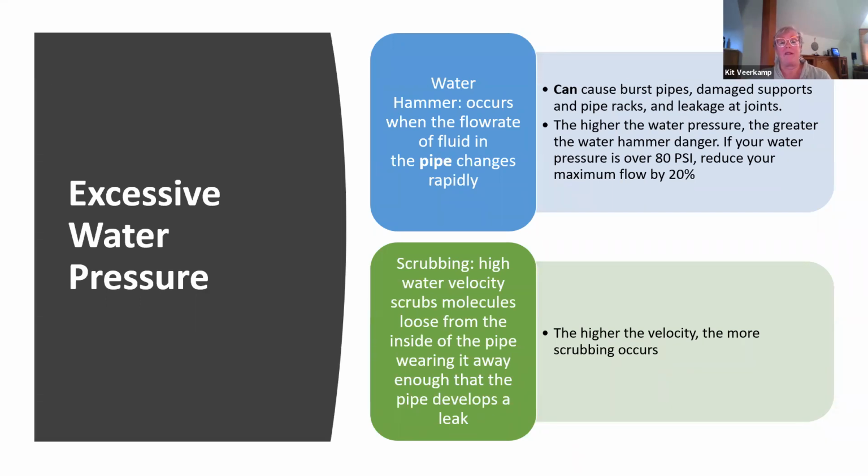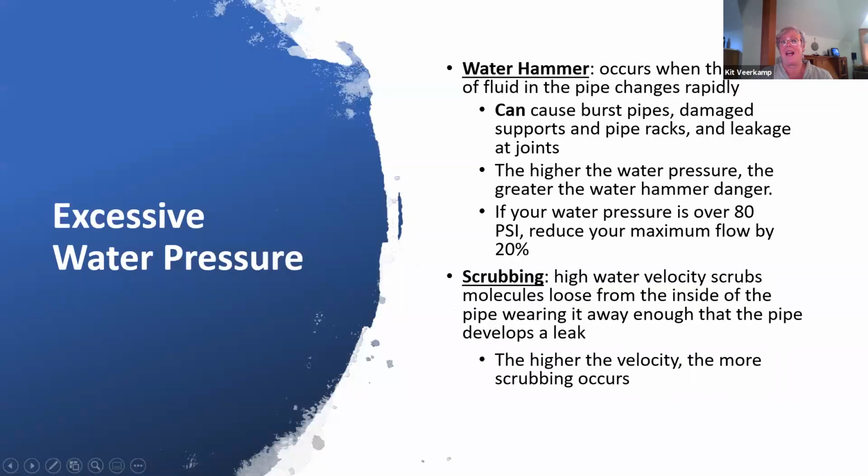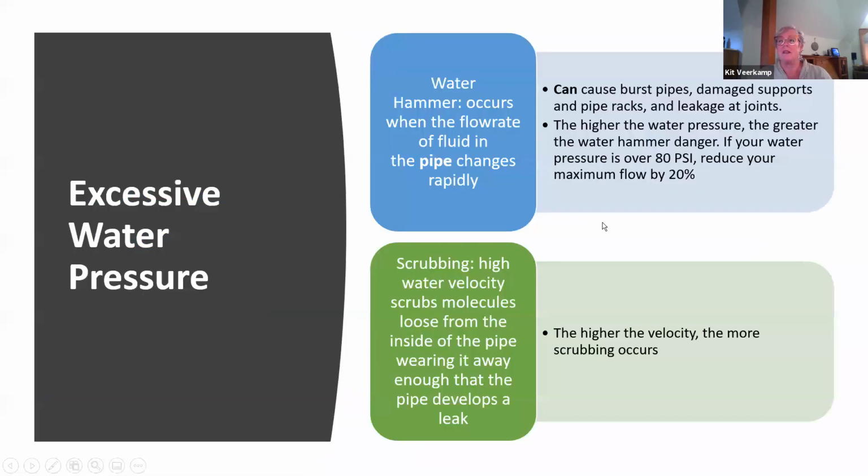Other things happen when you have excessive water pressure as well. You'll get water hammer, which causes your pipes to bang. And it's not just that. What happens is that continuous beating on the pipe wears it down, splitting it, and it will reduce the life of your system if you have that going on. So again, if you've got high pressure, it's easy to put on a pressure reducer and reduce that down to avoid hammer.